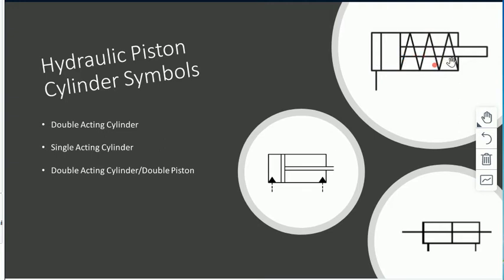And then obviously we need to get the piston back when we don't need it in the forward position. All that's done here is the pressure is released. We could do this with a pressure relief valve, or with one of the three-way switches where we just feed the pressure back to tank, and then the spring would just return the piston back to its original position.